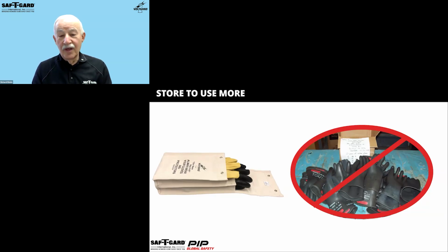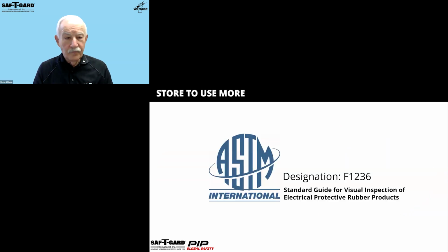If those protector gloves are wet or damp from working in inclement weather or perspiration or any other hazards, remove them from the rubber gloves. Allow them to dry. Remove the protector gloves so that the rubber gloves and protectors can both be inspected before the start of the next workday. And store them in a dry and cool location away from sources of ozone and direct sunlight. That's the way to store them safely.